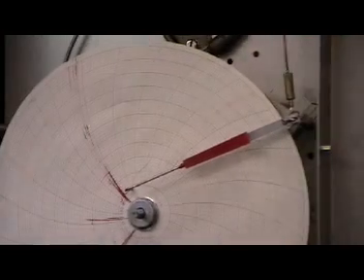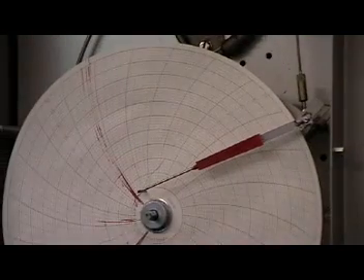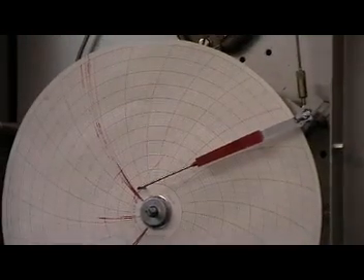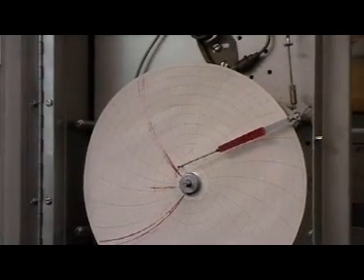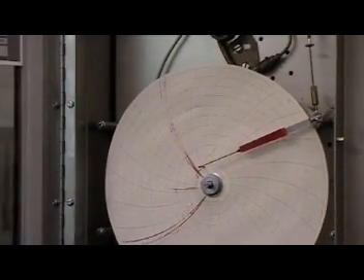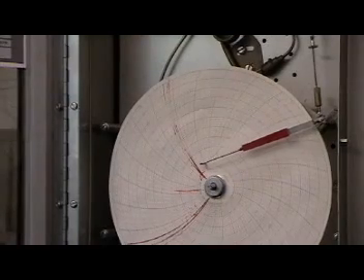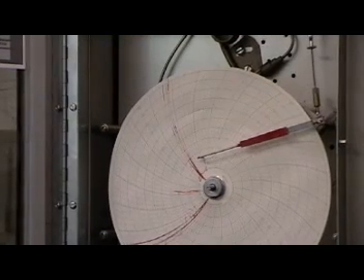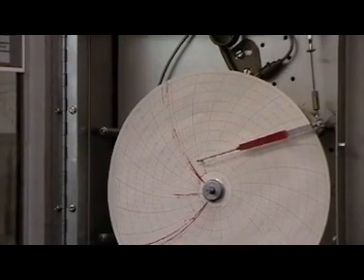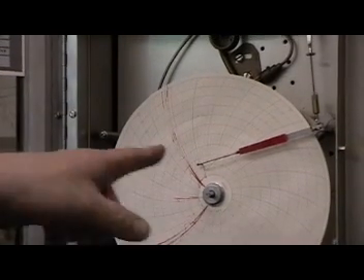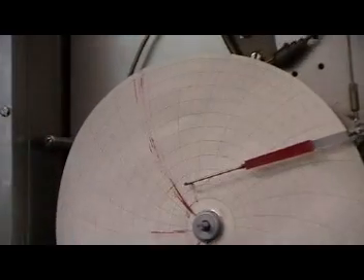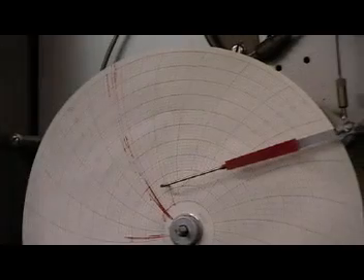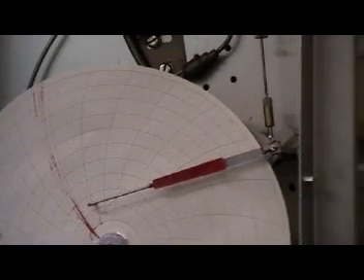That should be applicable in the center of the chart. Before you commence calibration, the first thing to check is that you have a mechanism with no backlash and that will repeat.